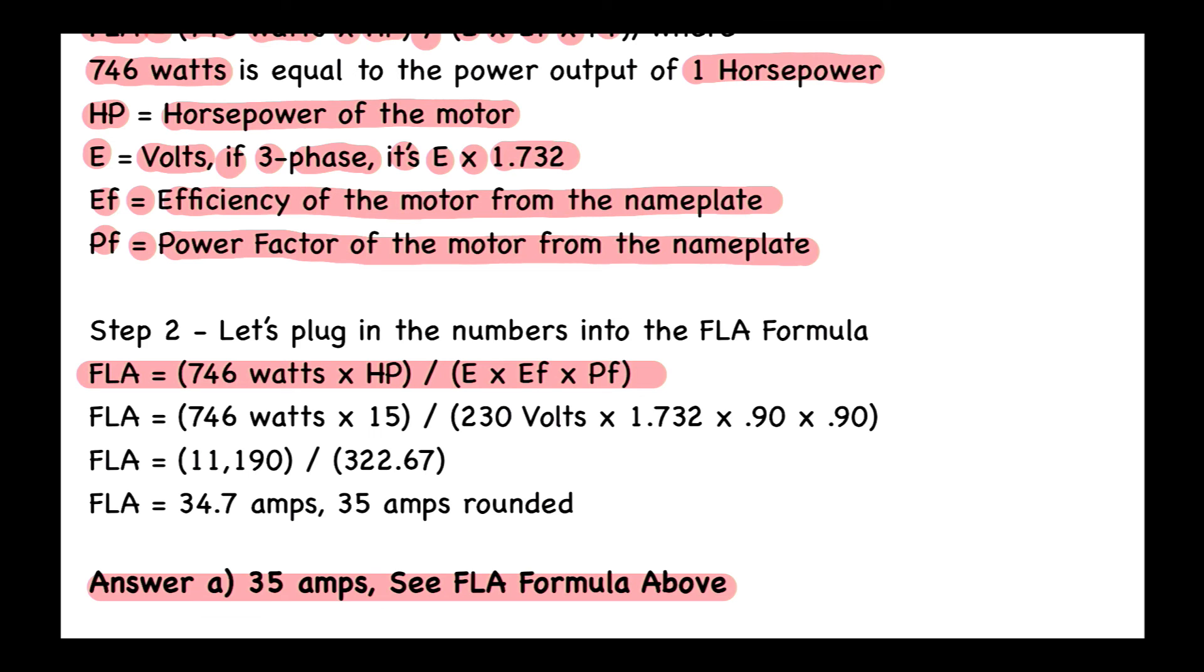Again, FLA equals 746 watts times the horsepower, and we take that and multiply those two numbers together, then we divide it by the voltage times the efficiency times the power factor. If you have a motor sitting around, take a look at the nameplate and enter those numbers and see if that's going to equal the FLA of that motor.